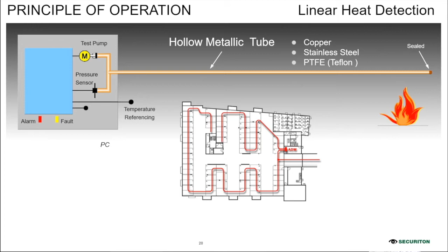The system triggers an alarm as soon as a defined limit is exceeded. And this defined limit can be programmed as per the requirement of the site, as per the requirement of the project. Two sensing tubes, if you can say, we have a single channel tube or two sensing tubes. If you use a two-channel, two sensing tube system, the coverage area will be double. The sensor tube can be of copper, stainless steel, or hard plastic, which is Teflon.